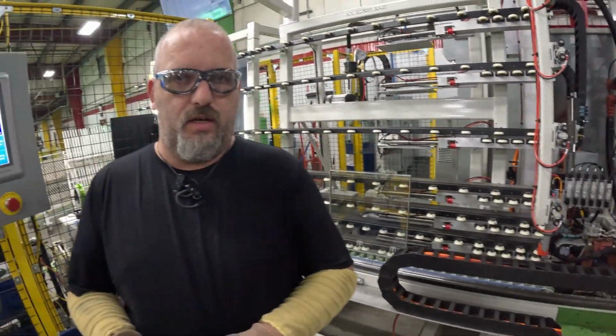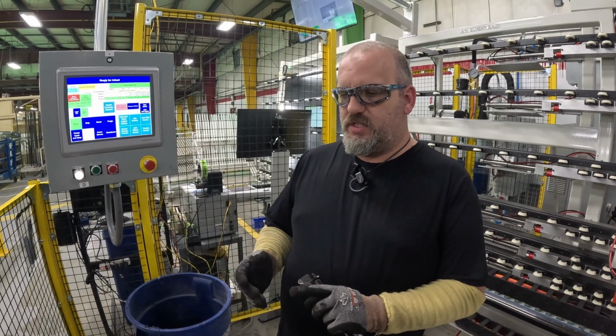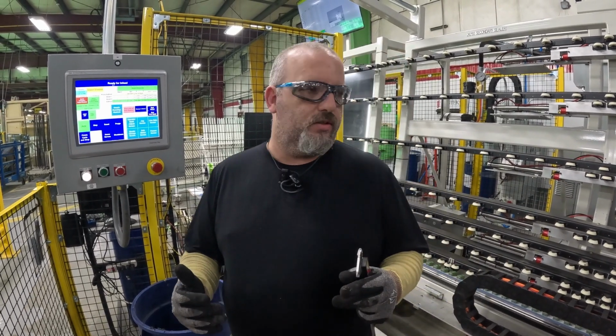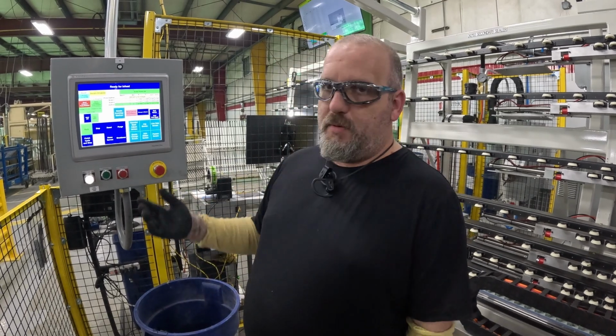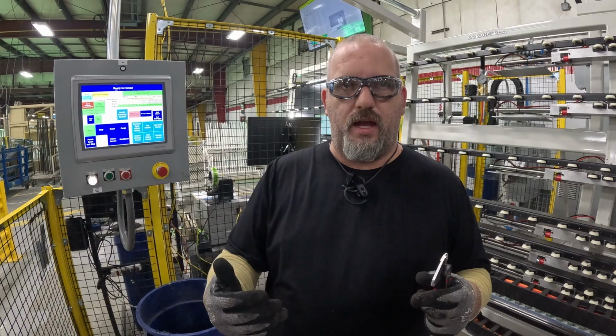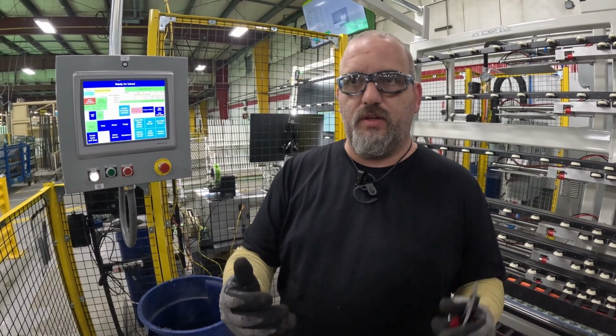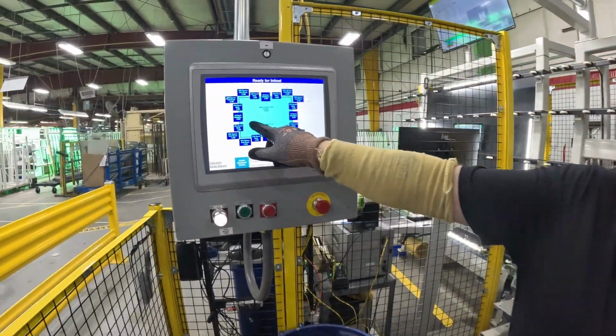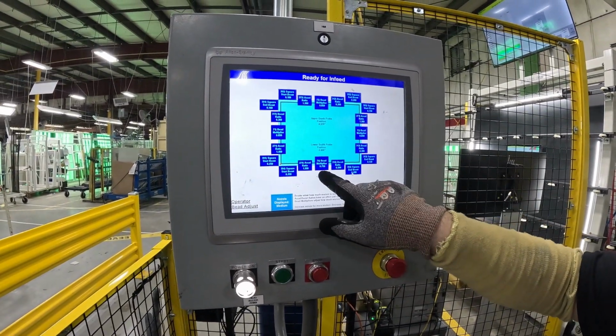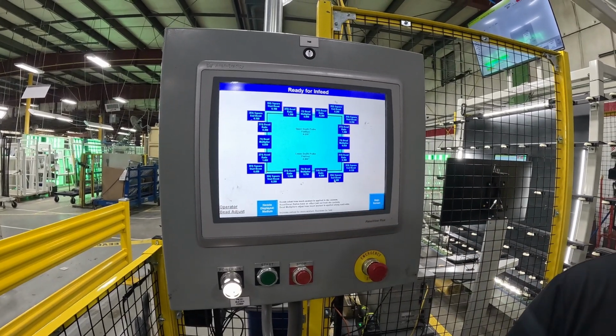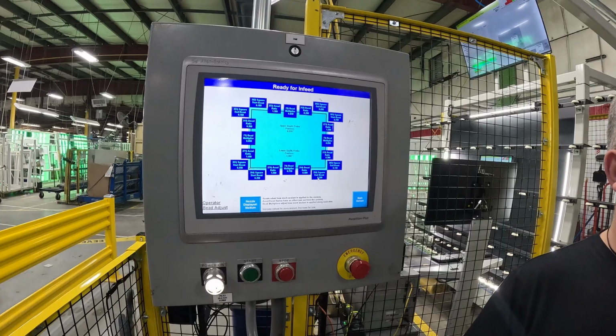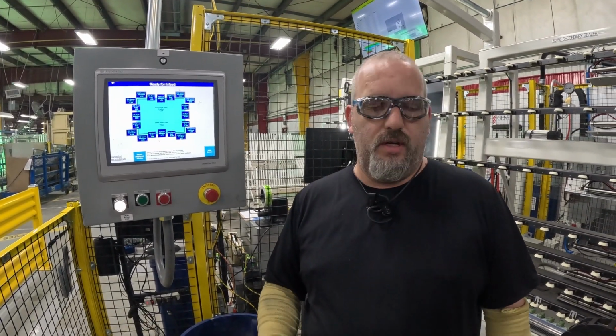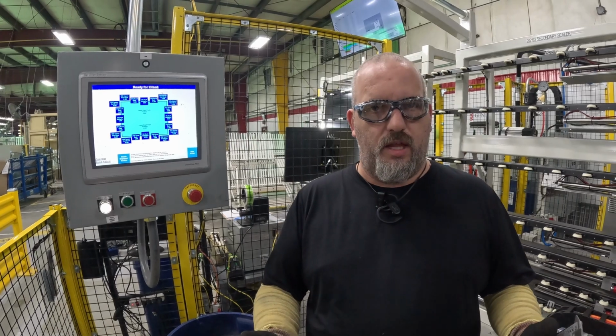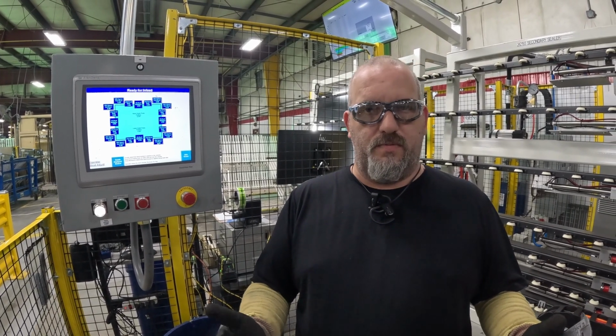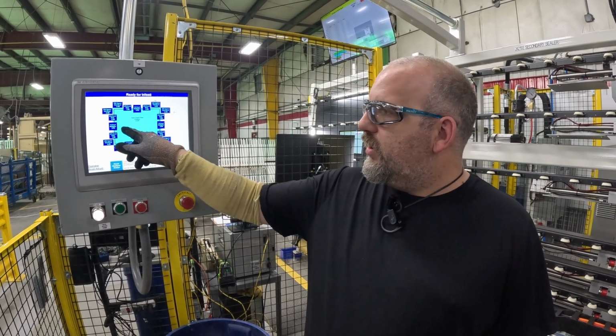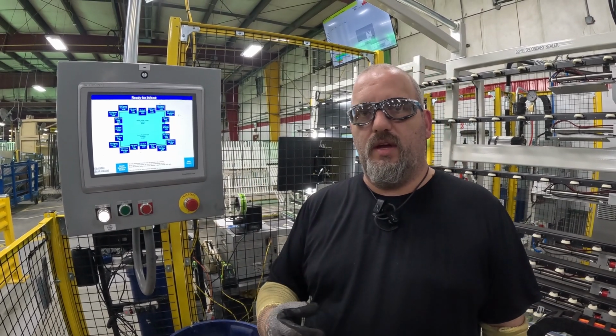The biggest thing on the sealer, the number one thing, if your sealant is looking way underfilled or way overfilled, check your depth probes. I mean, let's say the unit was underfilled on the trailing side, right? Or like, let's say across the board, the whole unit was underfilled. I could go to operator bead adjust, and I could crank up how much sealant with this bead multiplier we're putting in the unit, and I could fill that unit and make it look good. But it's likely because the depth probe is reading improper. So let's say the depth probe is reading 0.1 instead of 0.2. That's a big difference. I come over and I crank up that bead multiplier, it'll fill the unit.